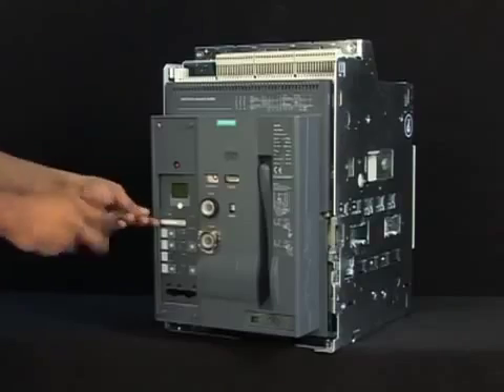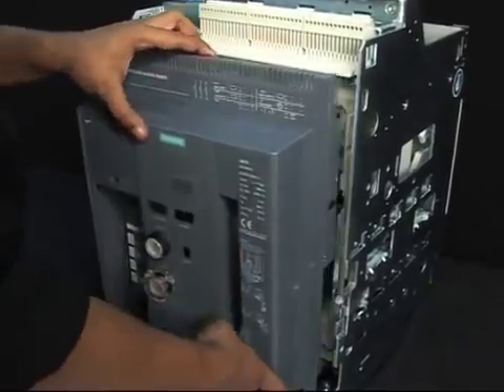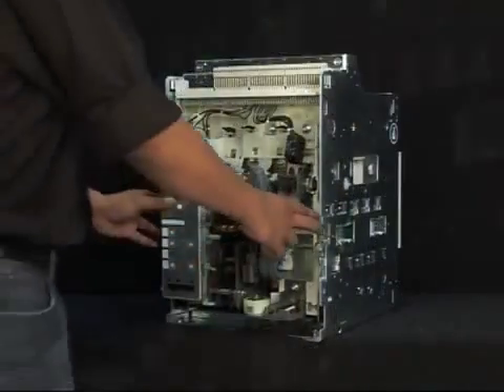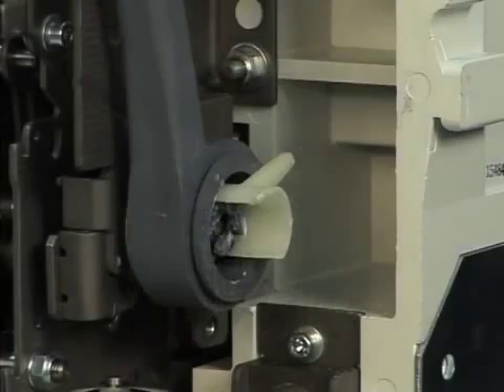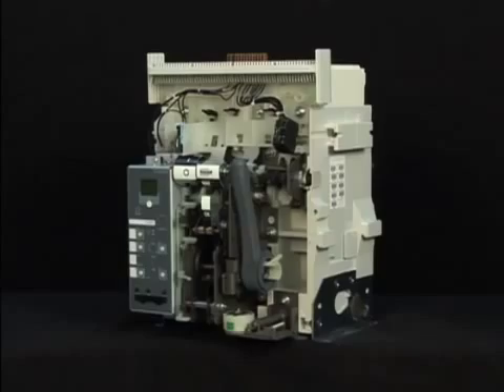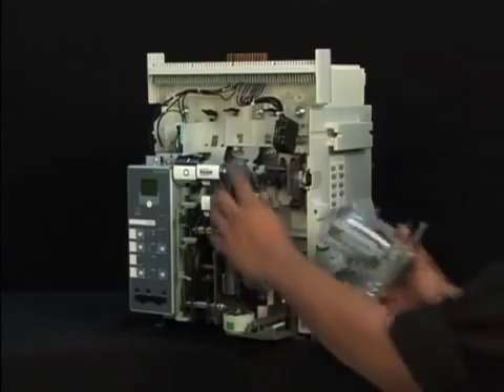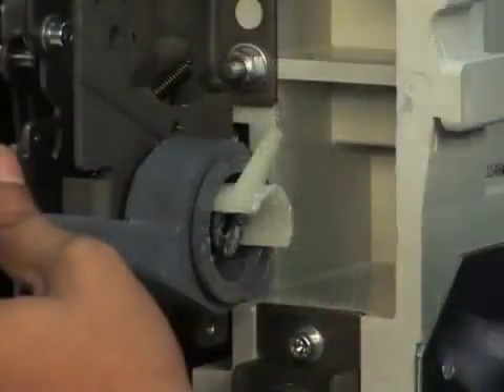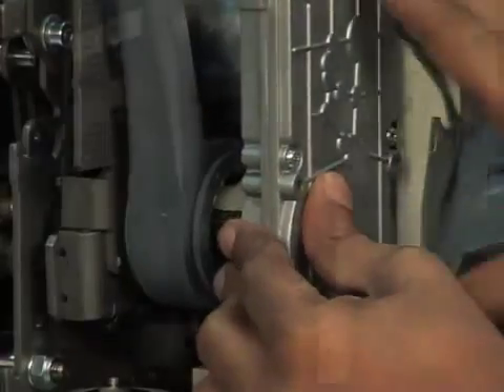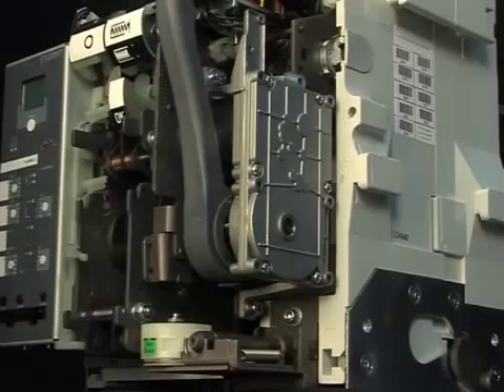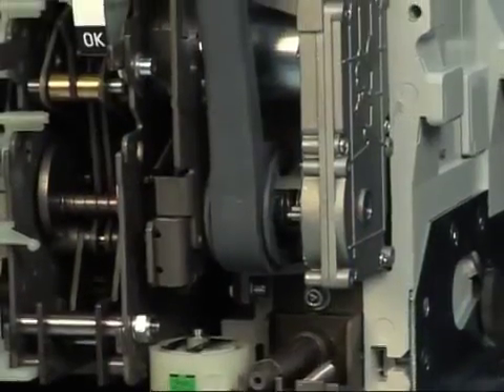Now, the front cover is removed by swinging down the charging lever. Now you can see the slot meant for the motor in the right-hand wall of the breaker. To fix the motor, you have to swing down the charging lever and fit the central shaft of the motor to that of the manual charging lever while the motor mechanism is inserted in the slot meant for it. And please be careful not to damage the wiring and components on the PCB of the motor.